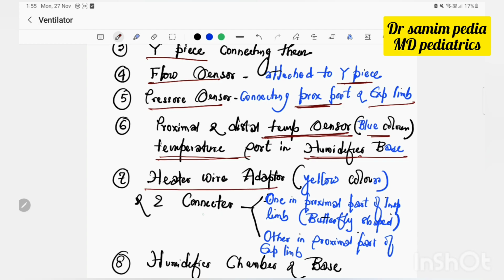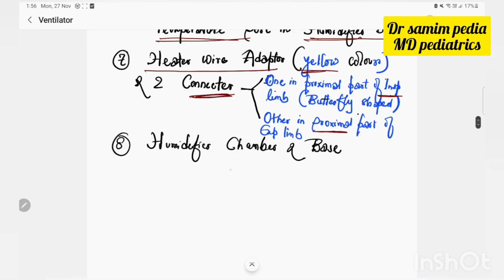Then heater wire adapter and connector. The heater wire adapter is yellow colored and it is present in the base of the humidifier. There are two heater wire connectors. One is connected to the proximal part of the inspiratory limb, which is butterfly shaped, and the other is connected to the proximal part of the expiratory limb. Then humidifier chamber and base.